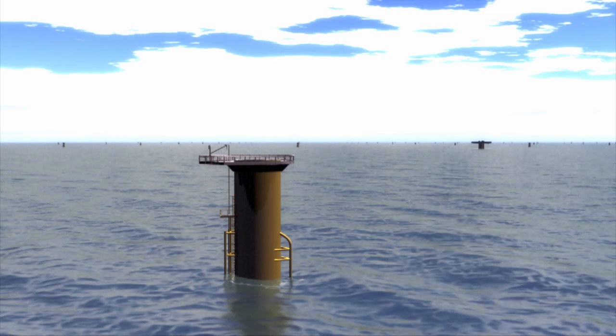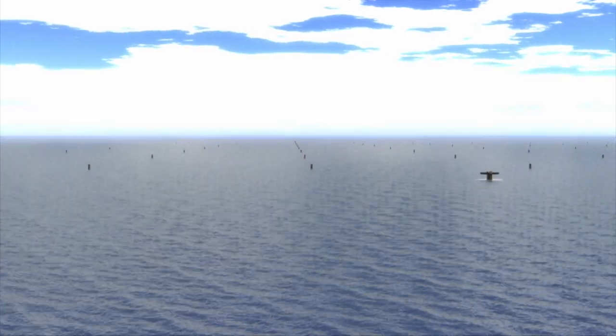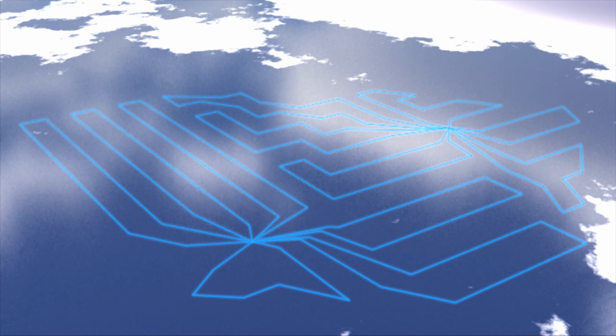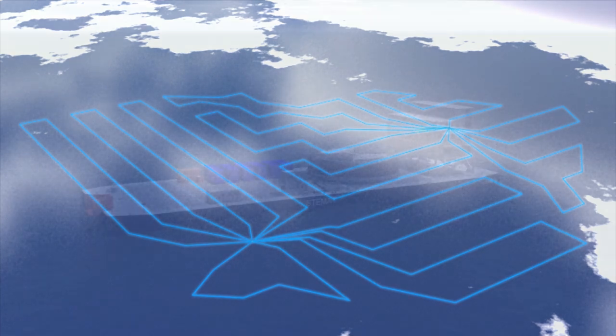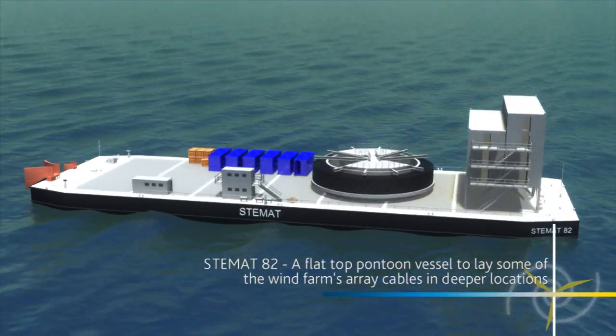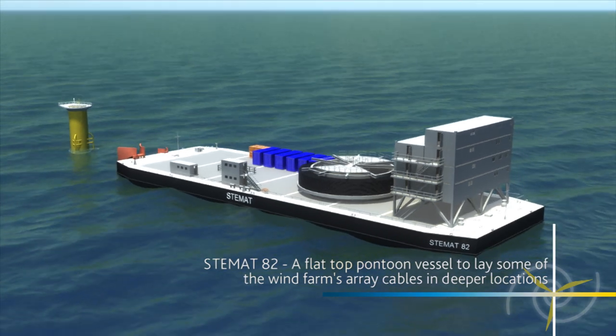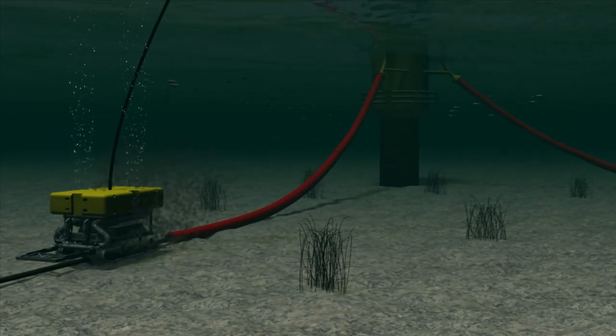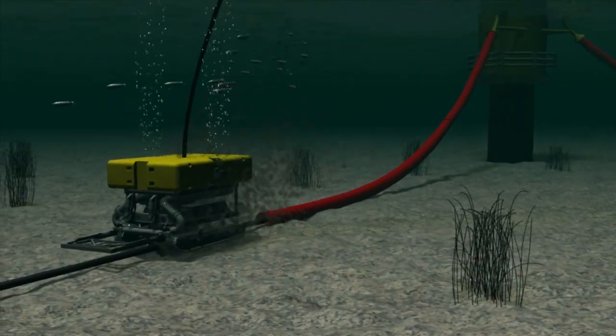The turbines are arranged in rows and columns, positioned to gain maximum power from the prevailing southwesterly wind. Placed up to a kilometre apart, they're connected to each other and to the offshore substations by array cables buried in the seabed. Specialist vessels will lay over 200 kilometres of array cables, connected to the turbines via J-tubes, and then jetted into the seabed using an underwater remote-operated vehicle.